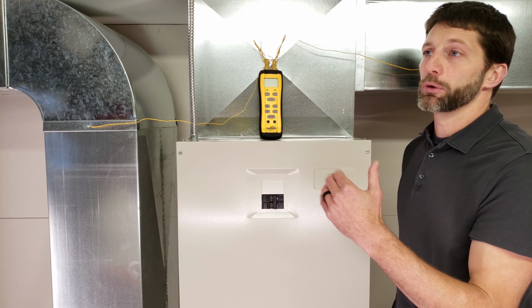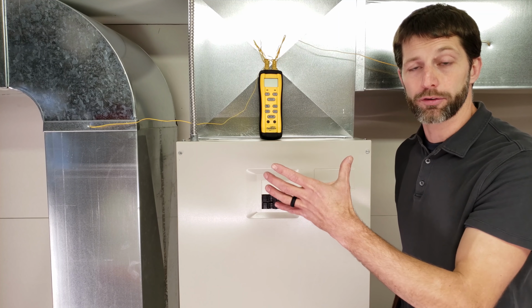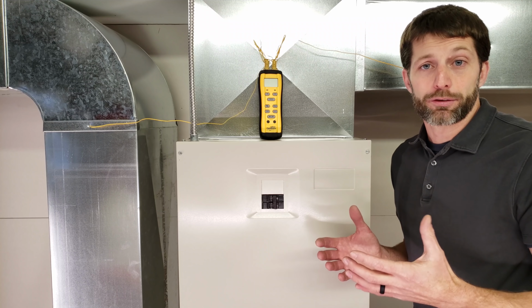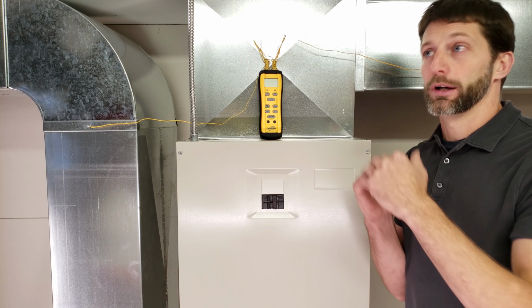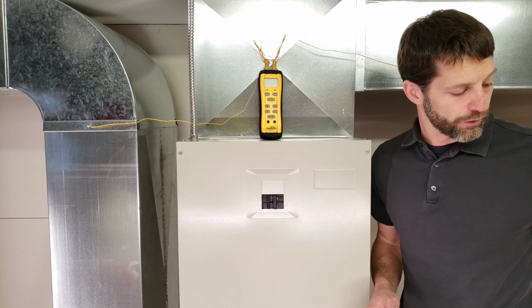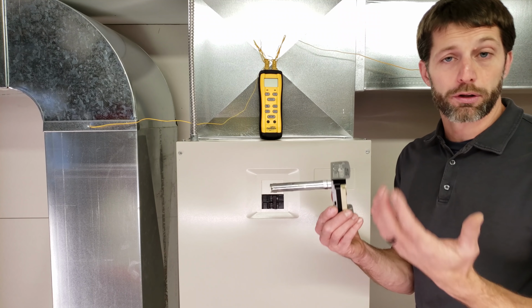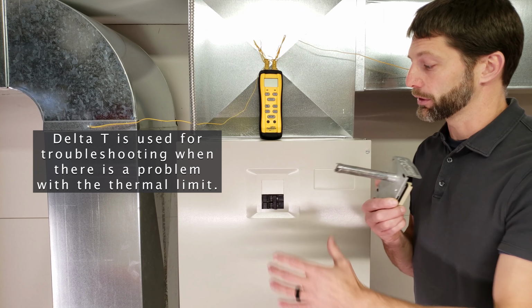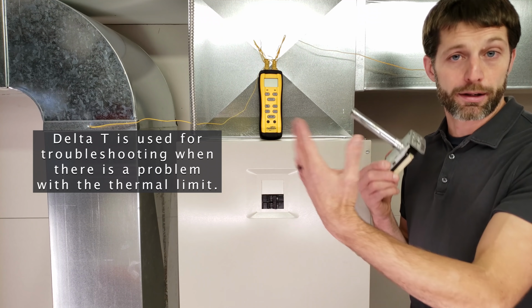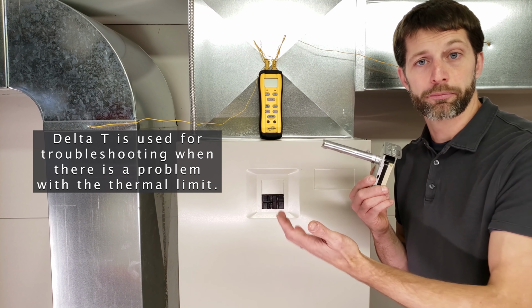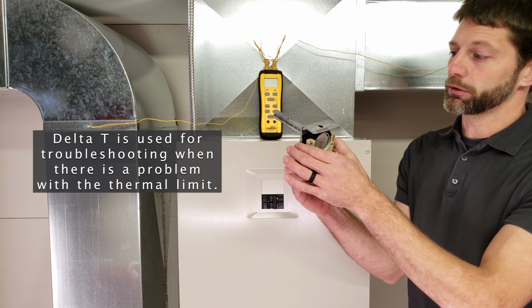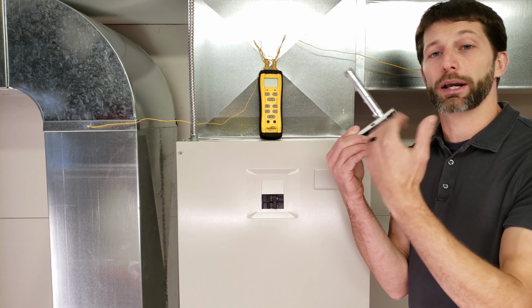So once that furnace is on and the blower is on for say 5 minutes or something like that, you want to make sure that your Delta T measurement is steady and it's not climbing. Because if it is climbing, whether it's an air handler or a gas or oil-fired furnace, then what that means is you don't have enough airflow to reject the heat into the building. And so one of your limits is going to trip, and it's going to stop the ignition, or it's going to stop the electric strip heating from providing the heat, but it's going to allow the blower motor to continue.